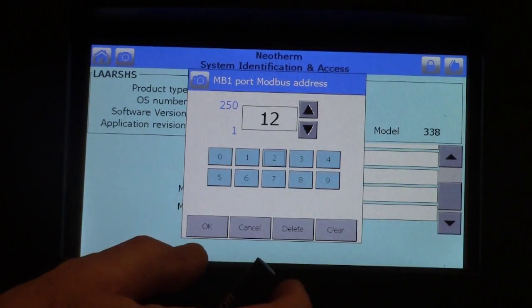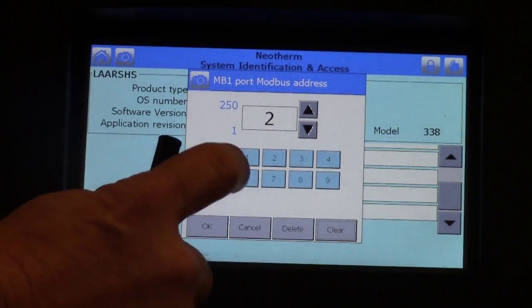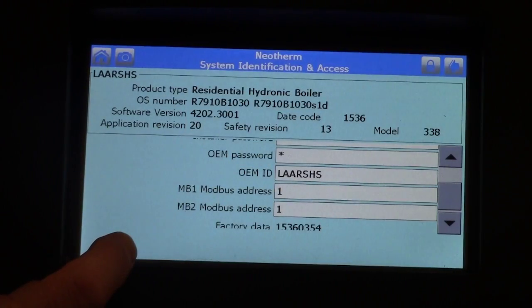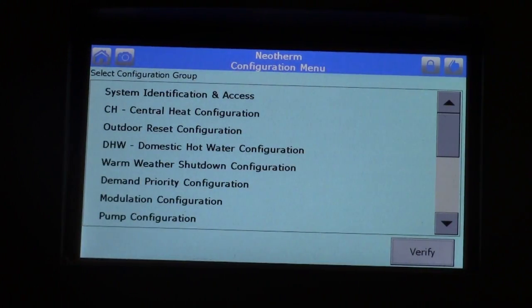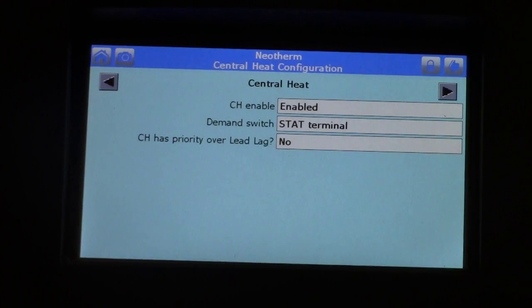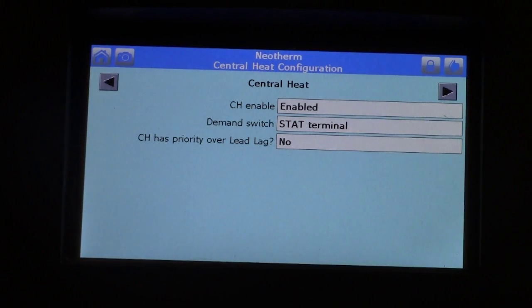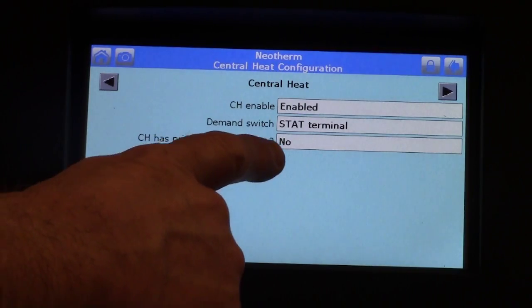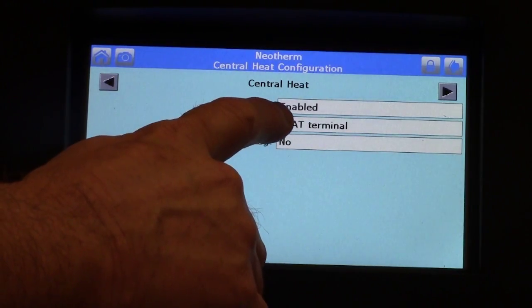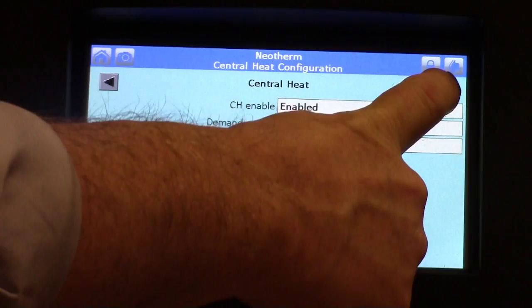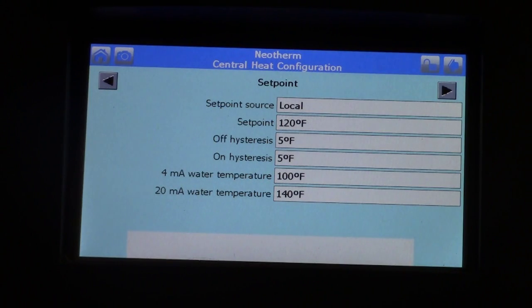I'll use the example of two — I want to bring it back to one. Use the down arrow, click OK. Now use the back arrow to get back to the previous screen. Next is the central heat configuration. Click on central heat configuration. Central heat should be enabled. Demand switch should be set to stat terminal. Central heat priority over lead lag is set to 'no' when we get into lead lag, but this is just a standalone boiler — all we want to make sure is that central heat is enabled. Hit the right-hand arrow and that brings us to the set point screen.